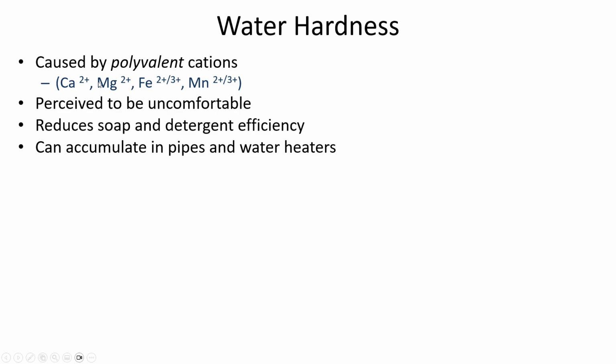Most inorganic constituents, most salts, most minerals become more soluble in hot water. But calcium carbonate is the opposite. It's less soluble in hot water. So you've probably noticed before that if you boil water in the same pan and you don't rinse it off, then there's going to be a white flake or some scaling that accumulates on it. And that is because of the inverse solubility of calcium carbonate.